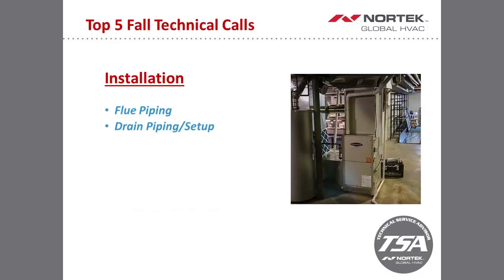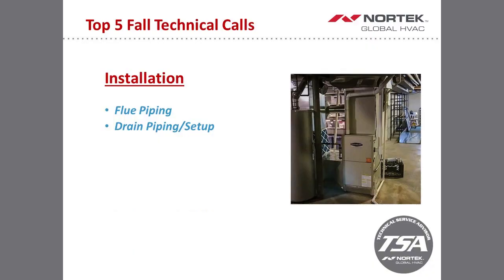The drain setup is pretty straightforward as far as using condensate pumps. Can we use condensate pumps? Yes, you can. Just make sure that the pipe isn't in the well of the condensate pump where you'd be double trapped. Also, with the drain setup, you just want to make sure that you prime any trap upon installation, or if you are servicing the equipment and you clean out the drains, just make sure that we reprime those because you probably will trip a condensate pressure switch if you don't.